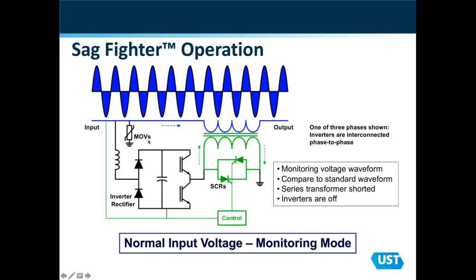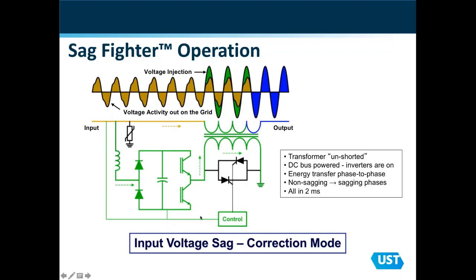So this is a representation of the Sag Fighter in standby mode, where it's simply passing good clean voltage on through to the load. We're watching the input with our control, and we have a series transformer that is shorted in the design with SCRs. And then here's our inverter. Now, when a sag event occurs, we recognize that with our control. We unshort the transformer, and with the inverter, we inject the appropriate voltage onto the appropriate phase, and we make that correction within 2 milliseconds, and we're able to maintain that correction for as much as 100 seconds.